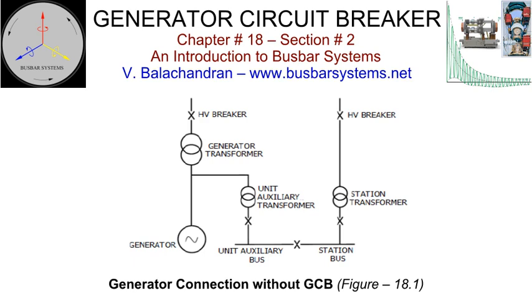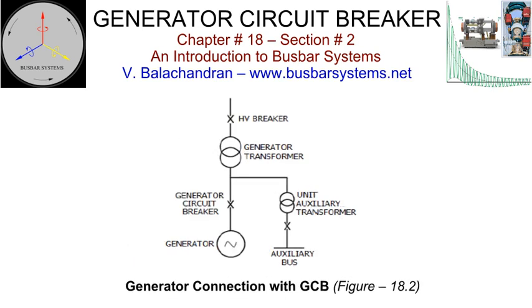For a plant where the generator is directly connected to a generator transformer, the auxiliary load is fed initially through a station transformer connected to the switch yard. Once the generator is synchronized to the grid through a circuit breaker on the high-voltage side of the generator transformer, and its unit auxiliary transformer is energized, the unit auxiliary load is transferred from the station bus to the unit auxiliary transformer bus for continuous operation. Such a scheme requires a bay comprising isolators, breakers, and instrument transformers in the switch yard. When a generator is connected to the generator transformer through a generator circuit breaker, the unit auxiliary transformer is energized through a back-feed from the generator transformer. The generator is synchronized by the generator circuit breaker at generation voltage, thereby avoiding a need for a station transformer and its associated bay in the switch yard on the high-voltage side and switchgear on the medium-voltage side.